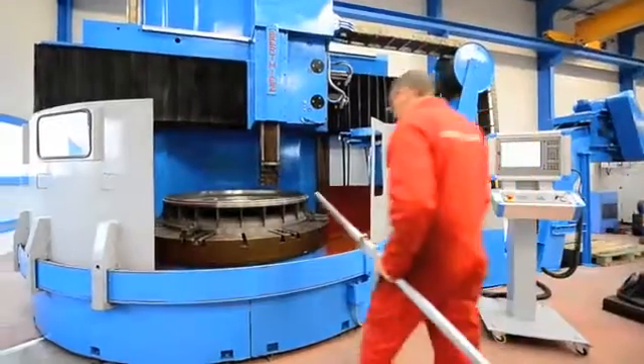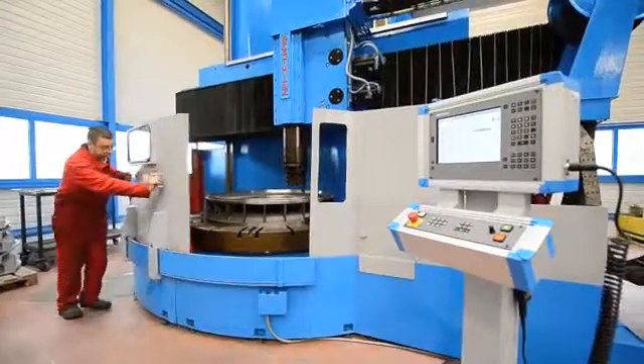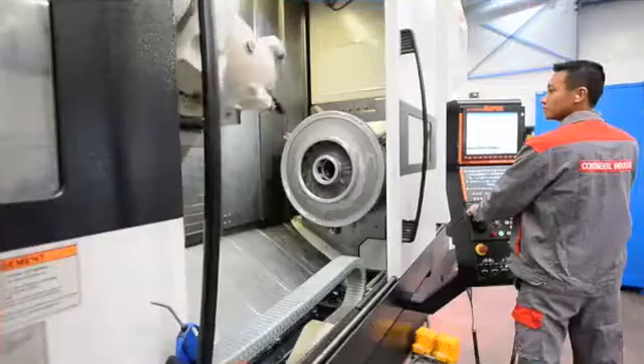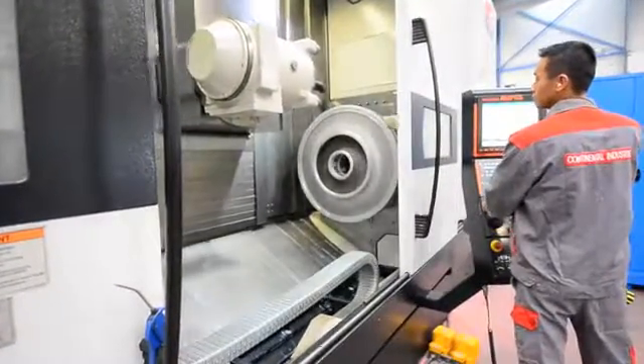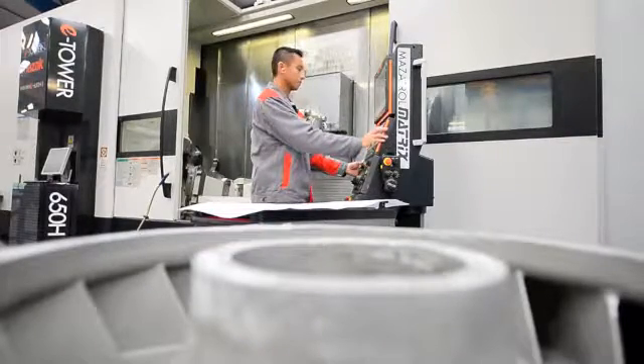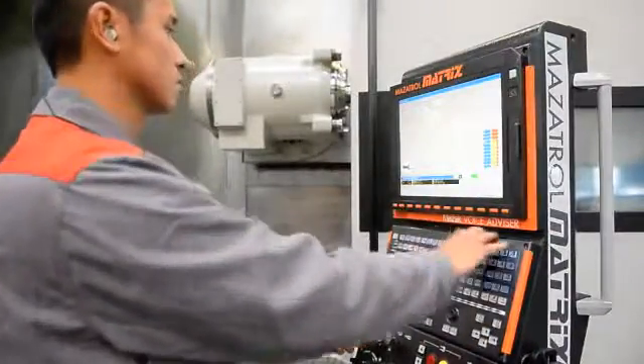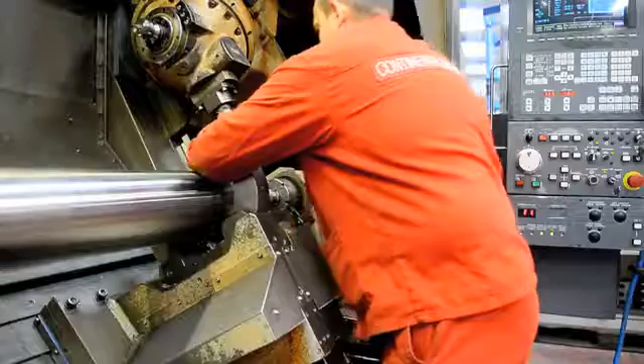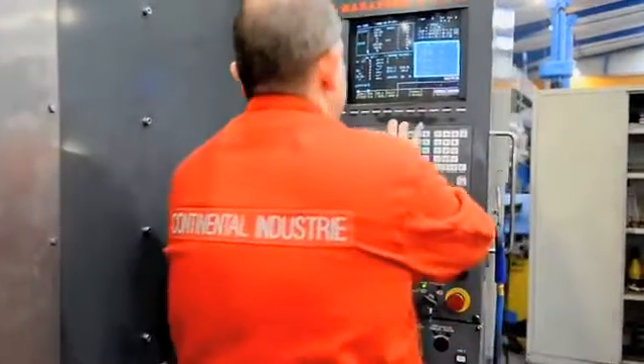using specific features as casing sealed by Loctite vacuum impregnation, nickel Heresite or Teflon coating treatment, stainless steel impellers and shafts, sealing ensured by double carbon rings or, in extreme cases, double mechanical seals, non-sparking drive guard, aluminium, ATEX dust or gas design, API 617 execution.